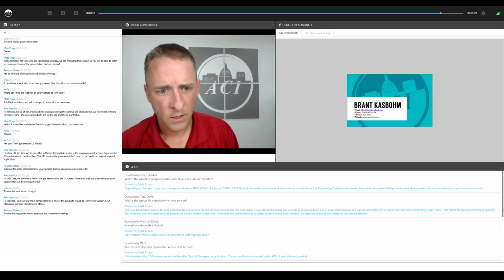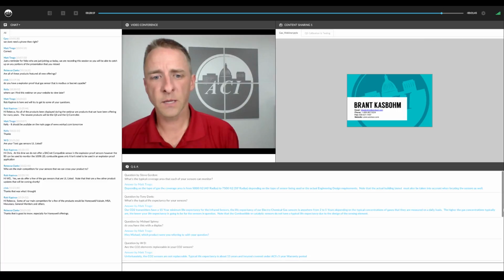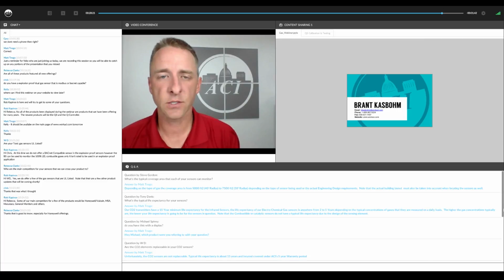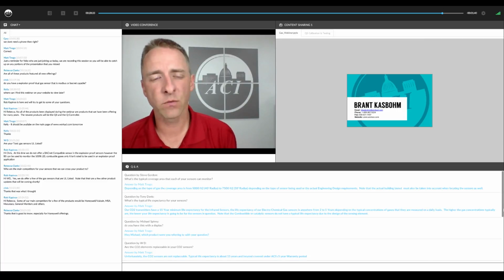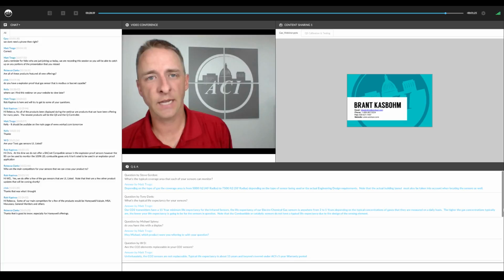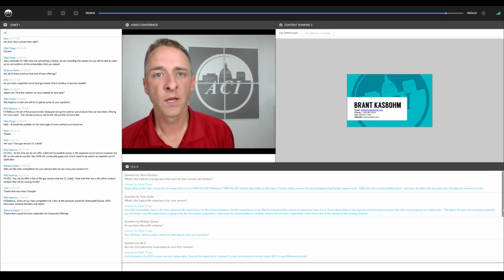Do you offer pre-measured calibration gases? No, we don't, and the main reason that we don't provide the calibration gas is because it's prohibitively expensive to ship it. Shipping tanks of gas, they're considered hazardous materials, even if it's an inert gas like nitrogen. Shipping tanks of pressurized gas is considered a hazardous material, and it's very expensive to ship. You can't just put it on a UPS truck.